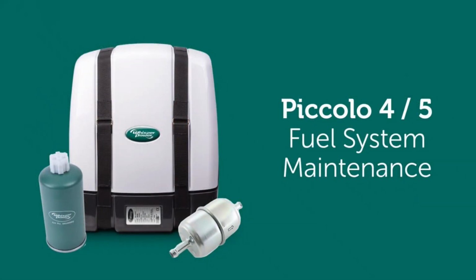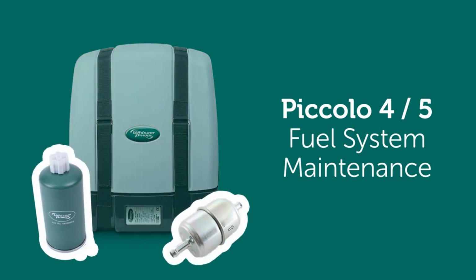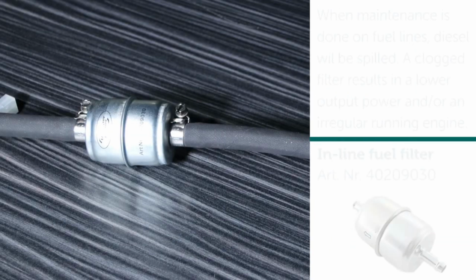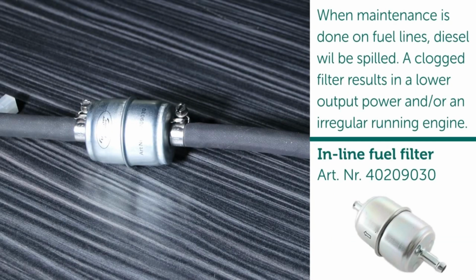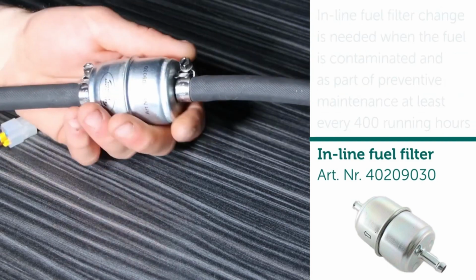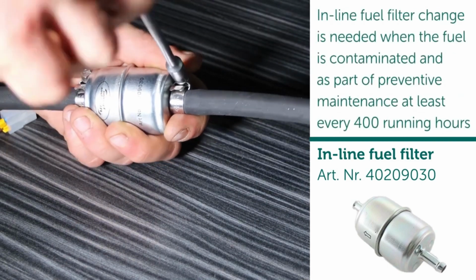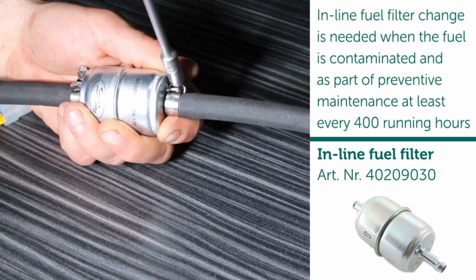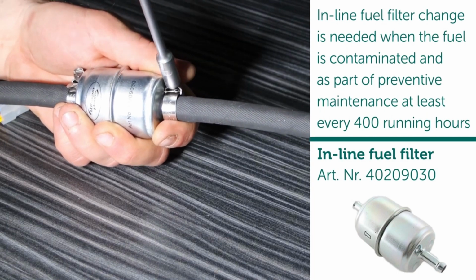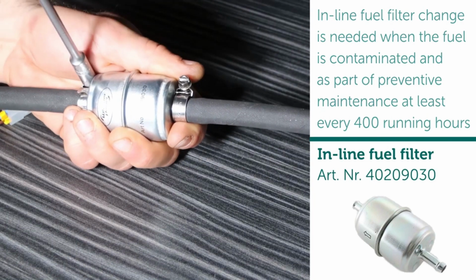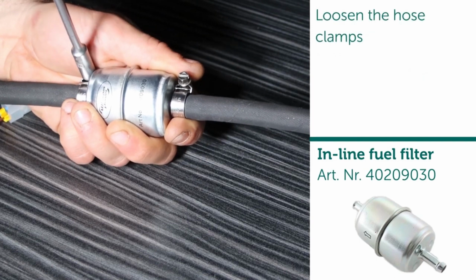Fuel system maintenance. When maintenance is done on fuel lines, diesel will be spilled. A clogged filter results in a lower output power and/or an irregular running engine. Inline fuel filter change is needed when the fuel is contaminated and is part of preventive maintenance at least every 400 running hours. Loosen the hose clamps.